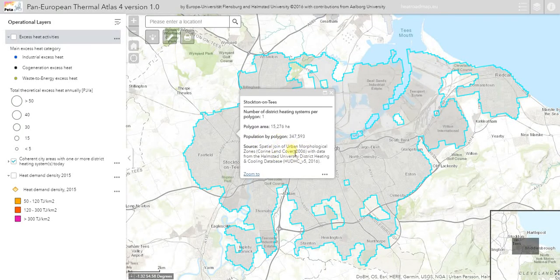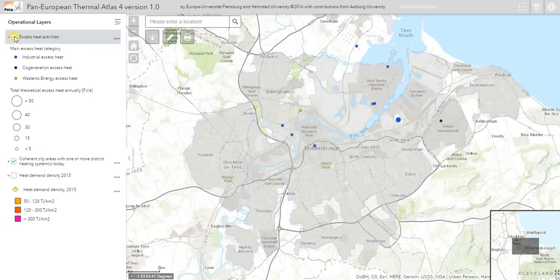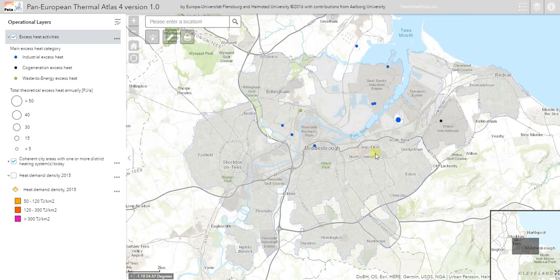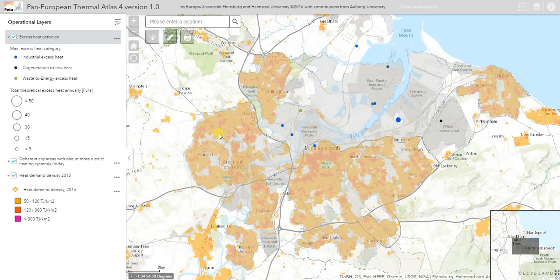Once this information is displayed, you can compare the heat demand in the city to the amount of excess heat located nearby. If the heat demand in Middlesbrough is 10 petajoules per year and the excess heat from nearby facilities is 35 petajoules per year, then all of the natural gas currently used in Middlesbrough could in theory be replaced with excess heat that is currently being wasted. Turning on the heat demand density map, I can then use the measurement tool to see how to get started.